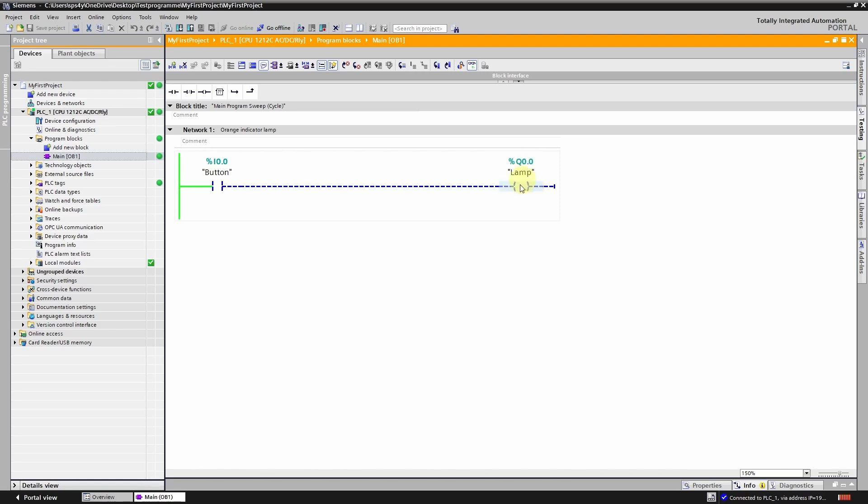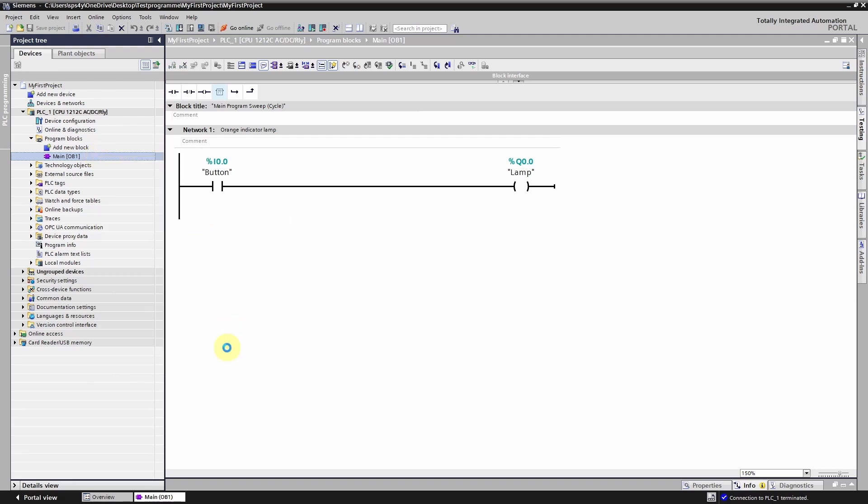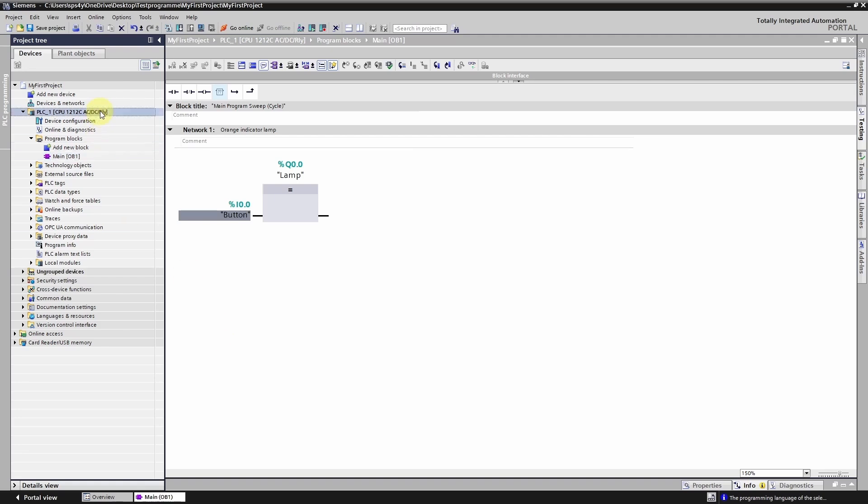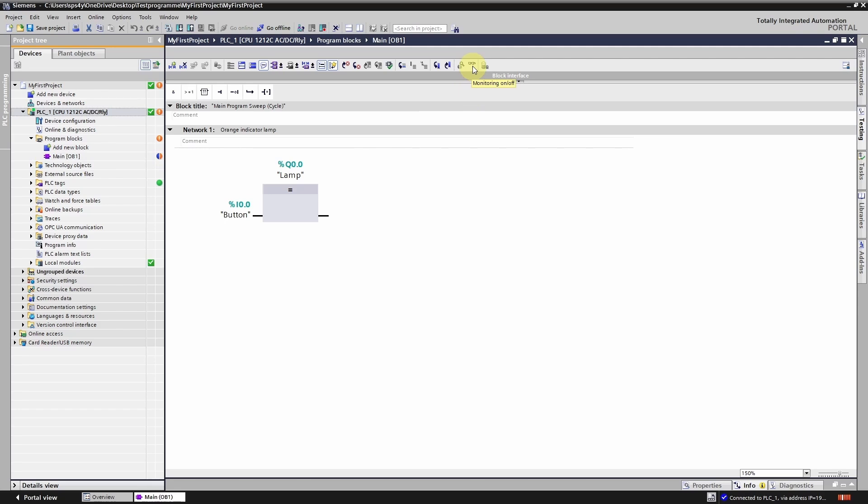Next I will switch the programming language to FBD. The color of the circle next to OB1 has now changed. The TIA portal uses the symbol to indicate that the offline project on your computer is different from the online project in the PLC. If this happens you won't be able to monitor the program. You will need to download it again.